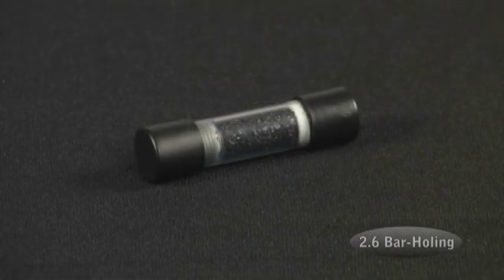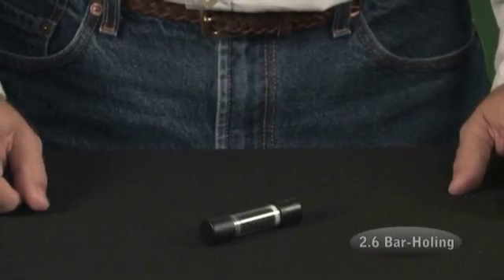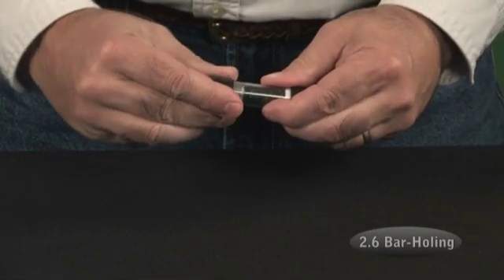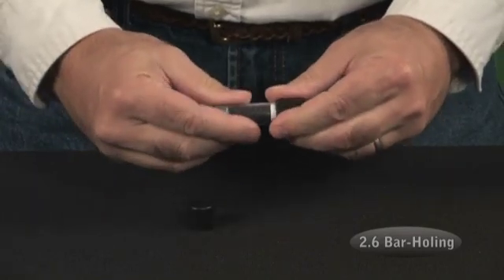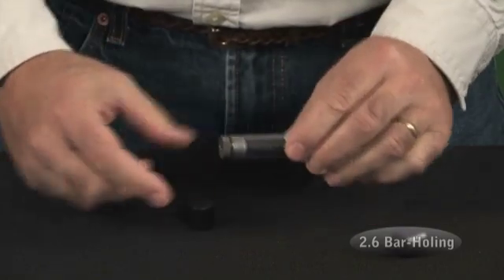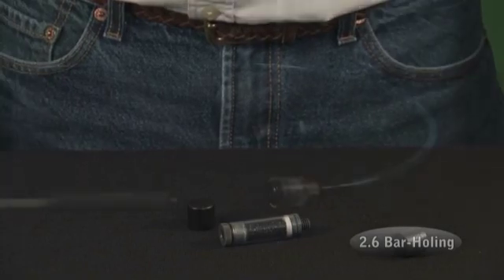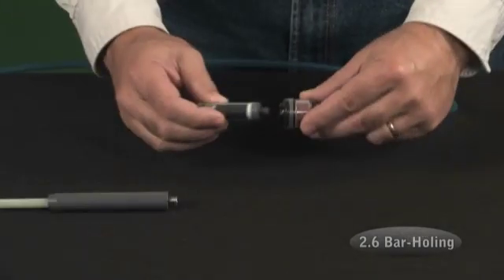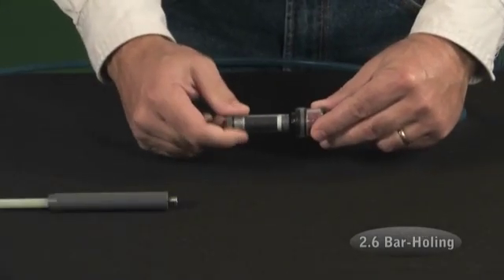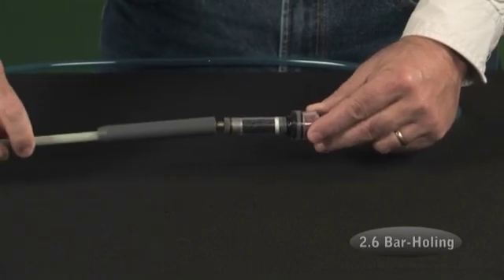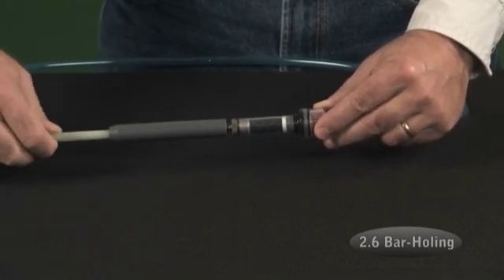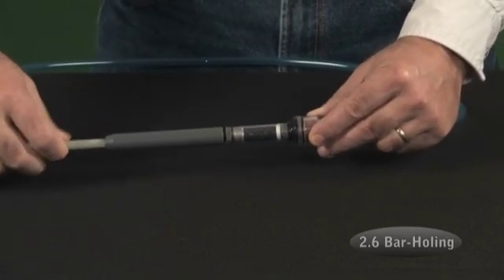If you need to bar hole in the vicinity of gasoline stations, or you smell gasoline, use a heavy hydrocarbon filter to remove gasoline from the sampled gas. The heavy hydrocarbon filter uses charcoal to remove gasoline vapors. Keep the filter capped at both ends until just before use. Install the filter by screwing it into the primary filter and then attach your bar hole probe to the other end of the charcoal filter. Discard the filter after use.